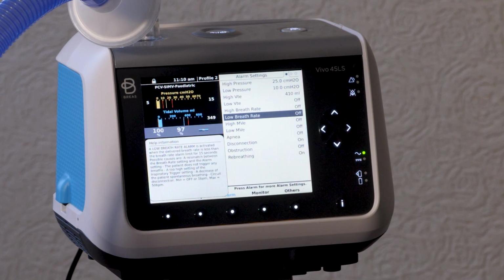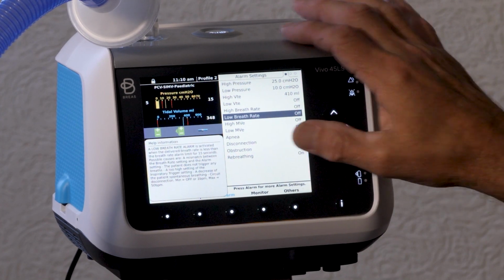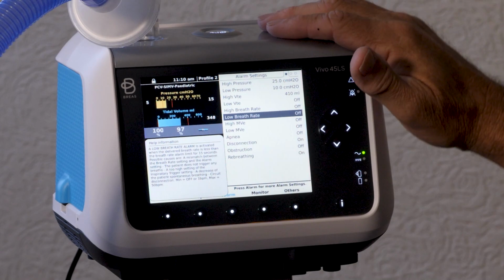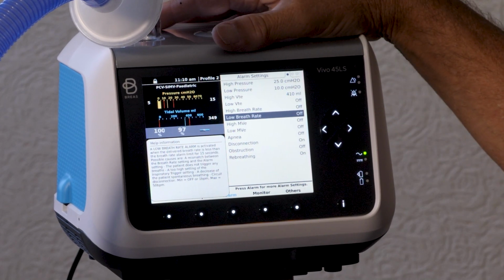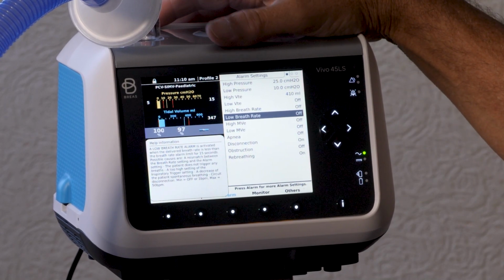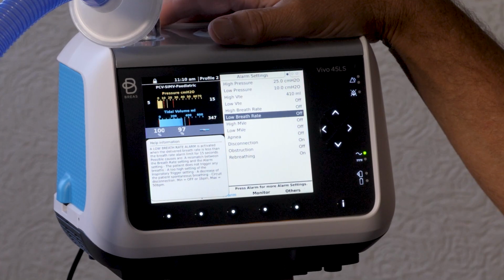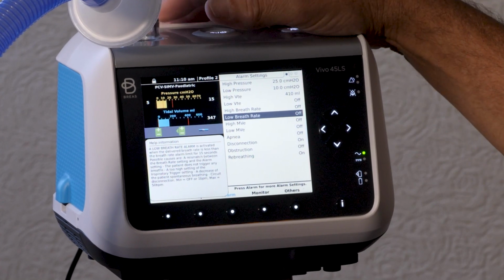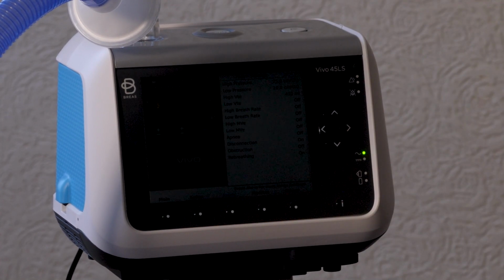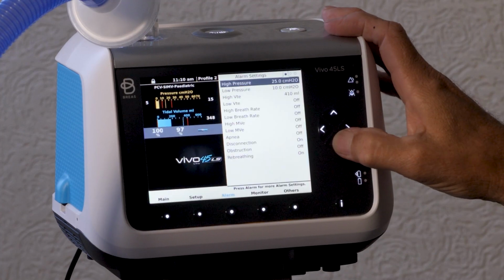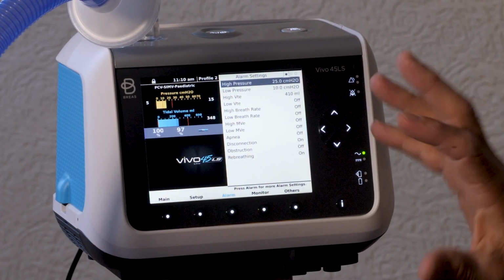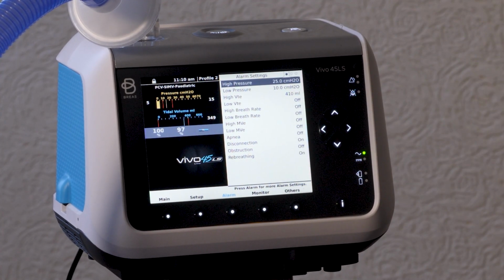And depending on where the alarm is set, it could mean a couple different things. If the alarm is set just below the programmed respiratory rate setting for the ventilator, then that could mean that the ventilator is not functioning properly and it's not giving the minimum required amount of breaths that it's supposed to give. So low breath rate alarm, check the patient first, and then you want to make sure the ventilator is giving the appropriate amount of breaths that it should be giving.